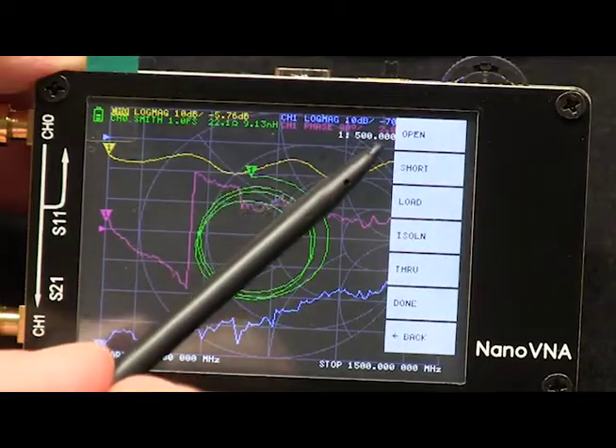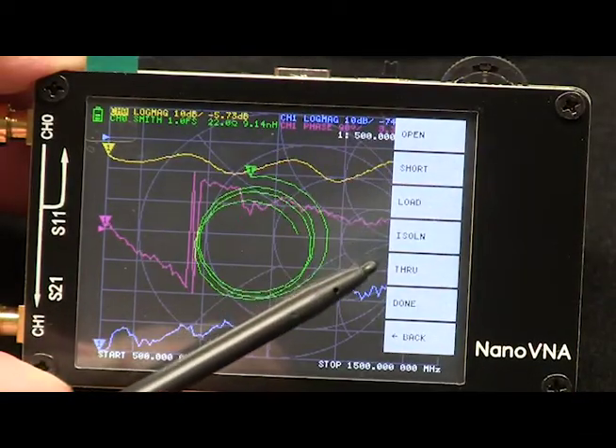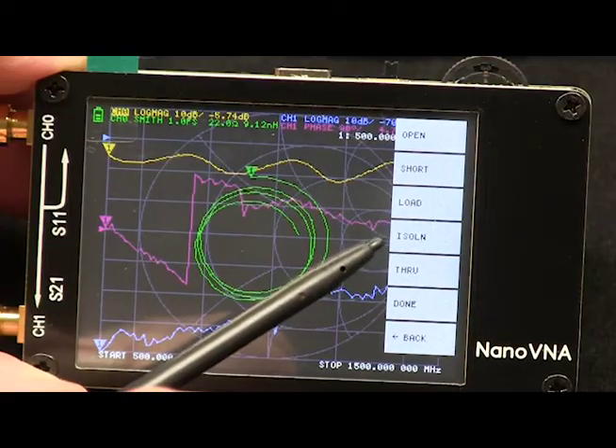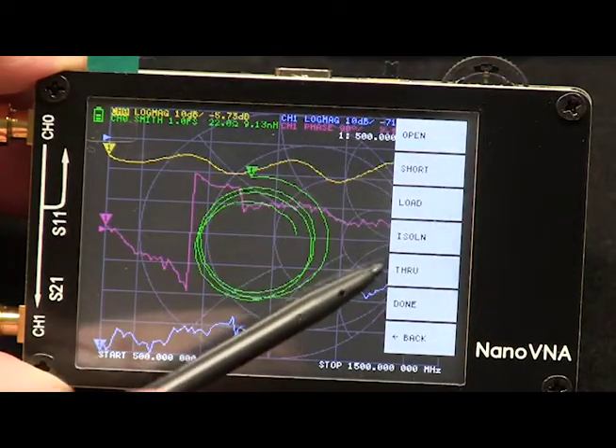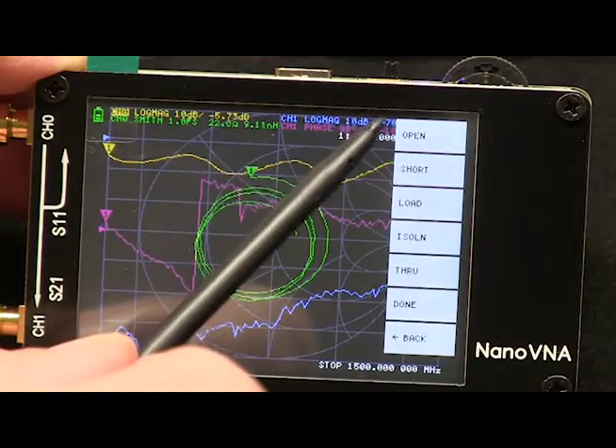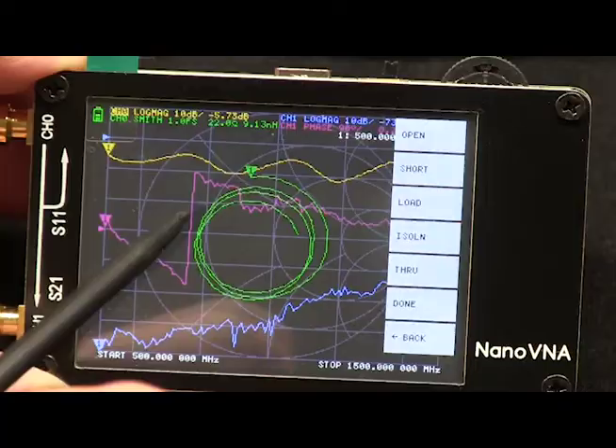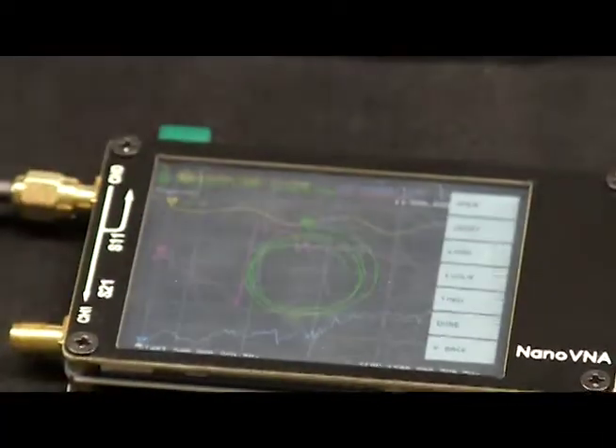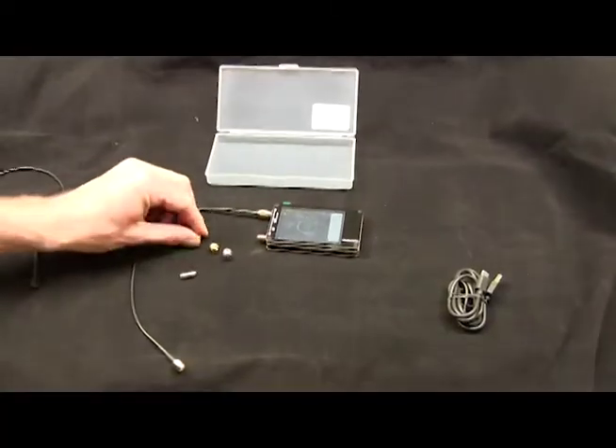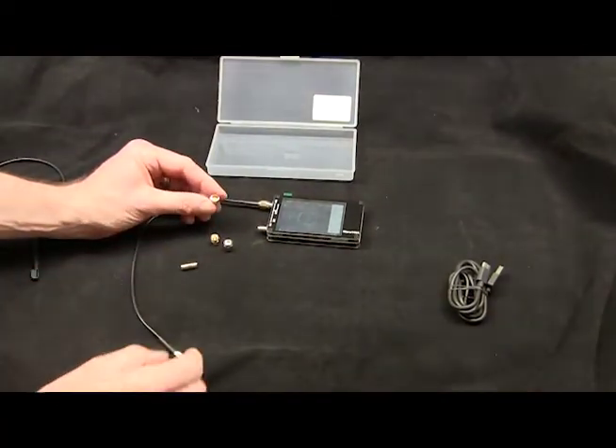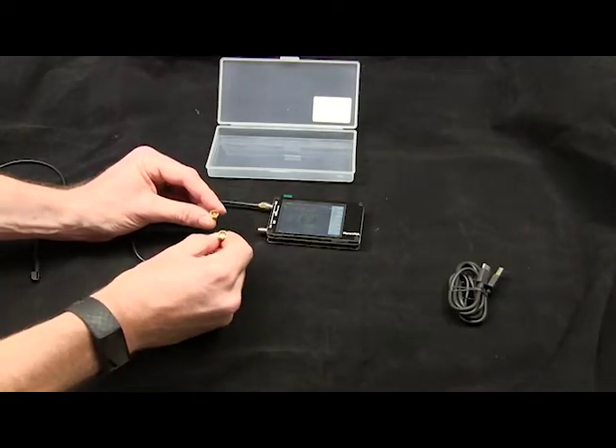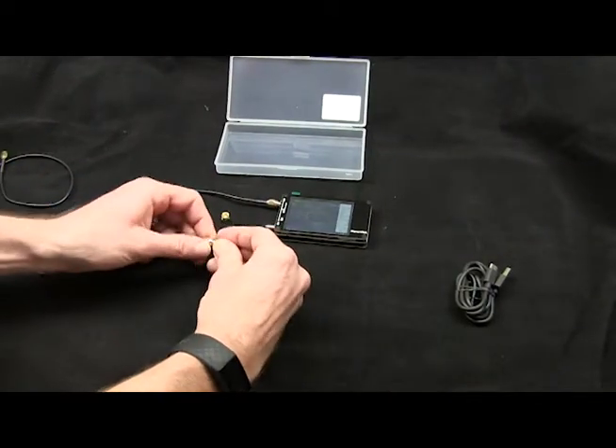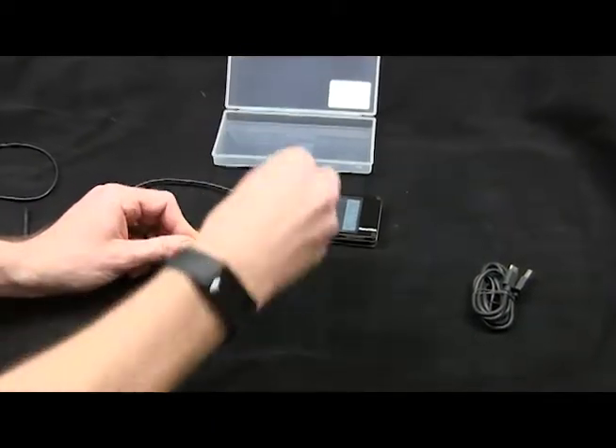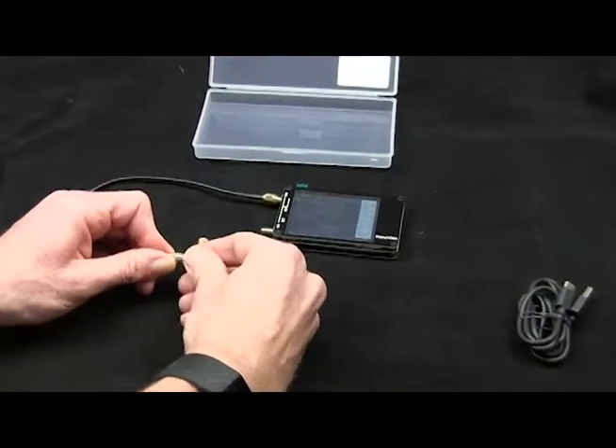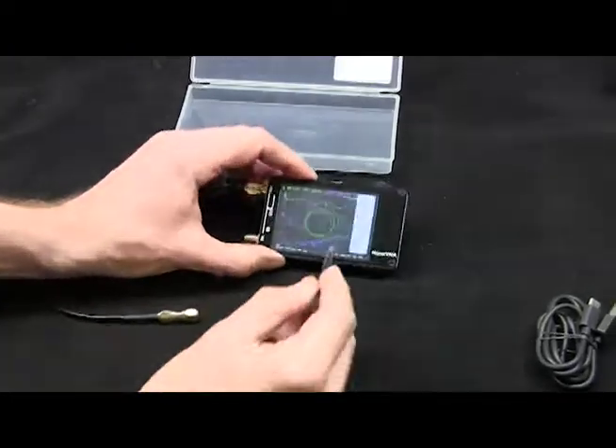You can see we have open, short, load, isolate, through, and done. We're not going to do isolation. We're just going to do open, short, load, and through. And what you'll do is you'll go through and attach the connector for each one of these and click it when you do. So here we'll zoom out. And our first one is an open. So I'll take the one that has no pin inside. And you can see I can't connect it to the cable directly. So what I'll do is I'll connect the adapter. And then I will connect the open, and then I will simply click the open button and it will calibrate the open.